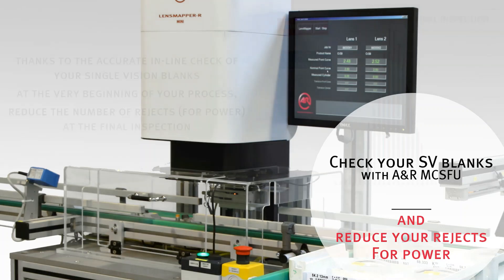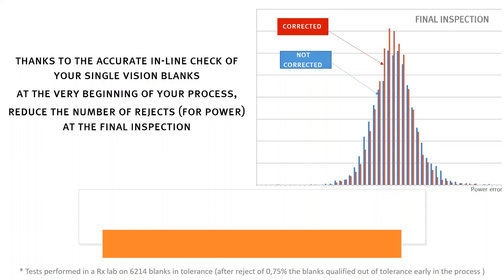Let's review the data provided by a lab. The blue curve is the distribution of the error on power, which is measured during the final inspection of the lenses and without adding any compensation during the lens surfacing process. In contrast, by using the measured data collected through the MCSFU and applying the compensation during the surfacing process, the lab gets the red curve, which illustrates a much narrower distribution.